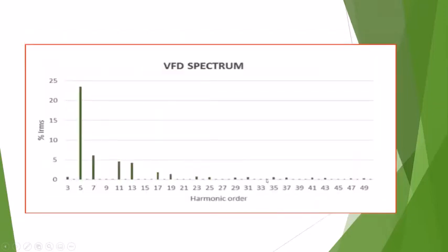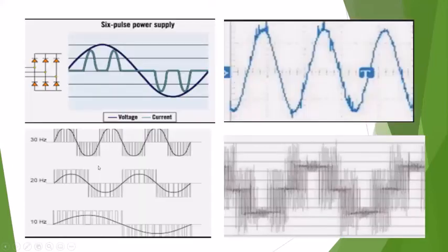So this is an idea of what you'll see in harmonics coming into a machine. Normally your third's not too bad. Your fifth and seventh are pretty high on a six pulse machine. But if you go to a 12 pulse input, the fifth and seventh are much, much lower, and even clear out through the spectrum of harmonics.